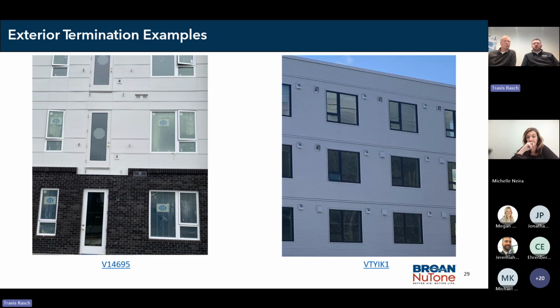We do get questions, particularly from code officials or AHJs, asking how you can have outdoor air being introduced right next to the stale air leaving the building. We have internal testing we've done and can provide that documentation. If you ever get asked, feel free to reach out to us. We've got internal documentation showing the contamination rate between the outdoor air being introduced and the stale air leaving the building is less than 5% with either of these two terminations.